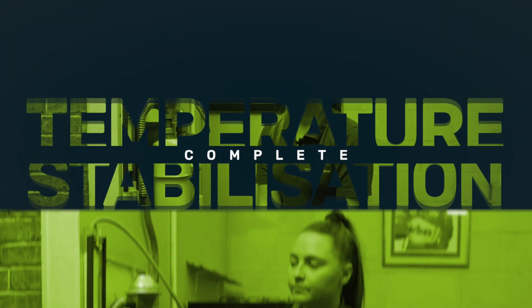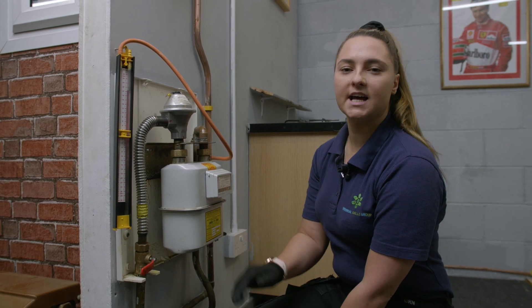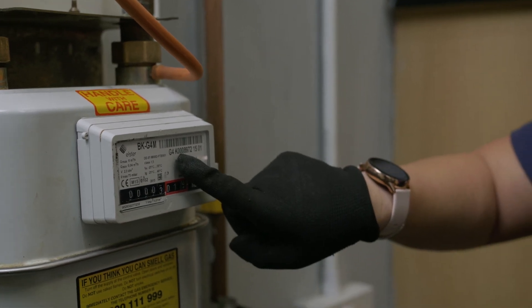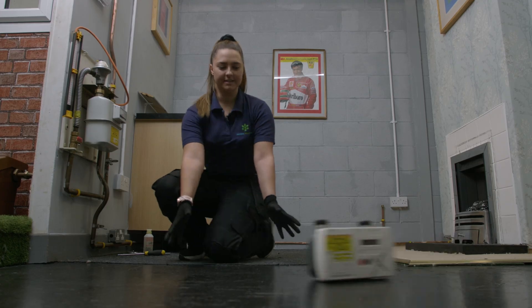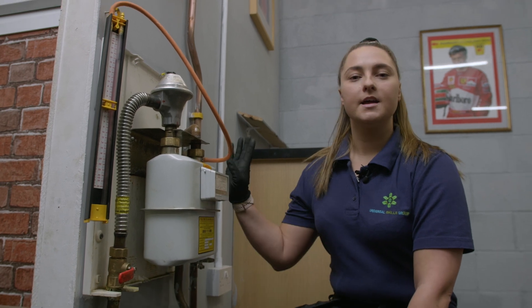Our temperature stabilization was okay, so we're going to carry on with our tightness test, which is going to last for two minutes. In this time we're testing the whole installation inside the house with the appliances connected. With this meter — we've got a G4 — over the two minutes it could drop four millibar, as long as there's no smell of gas, appliances are connected, and our pipework is under 28mm. If we had a U6 meter it would be eight millibar.